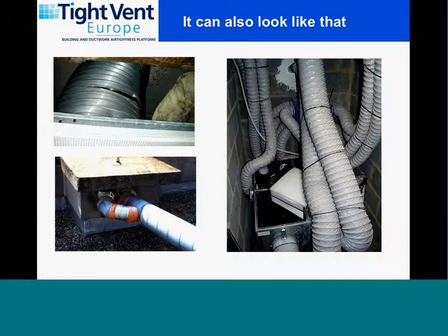We can see that obviously, if you look at, for instance, the bottom left picture here, there's a big leak, and probably a big fraction of the flow is going to leak out to the ceiling. And actually, in this case, it was a false ceiling, which was unconditioned.